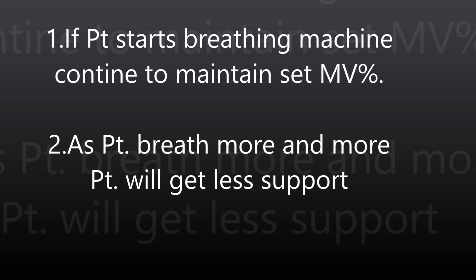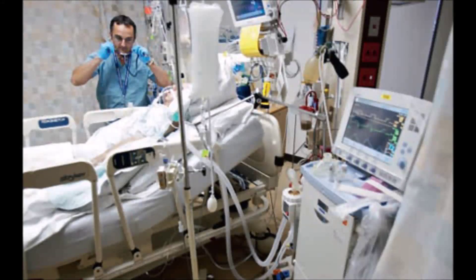The machine is also able to implement lung protective strategies to prevent complications, and as the patient breathes more and more, the pressure support will become less, just like as you would as an RT in clinical practice.